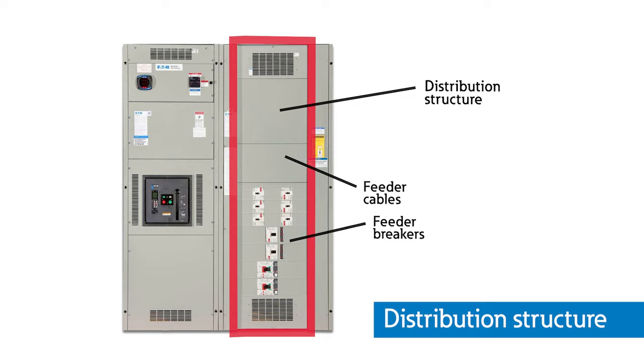Cables can enter through the structure from the floor, referred to as bottom entry, or from above, also known as top entry. Distribution structures divide and send power to branch circuit protection devices and then to branch circuits to power downstream loads. Power flows from the main structure to the distribution structure via cross bus or horizontal bus.